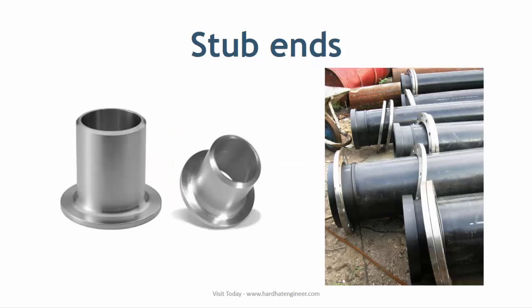Stub ends are used with lap joint flanges. In this type of flange, the stub end is butt welded with the pipe, whereas the flange is freely moved over the stub end. It is basically a flange part but covered under ASME B16.9, which is why it is considered a pipe fitting.